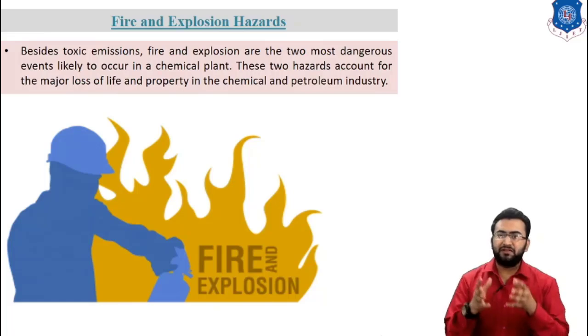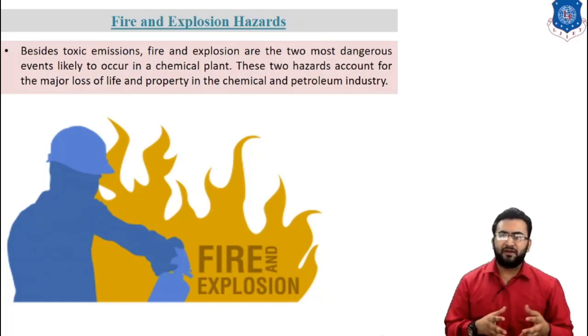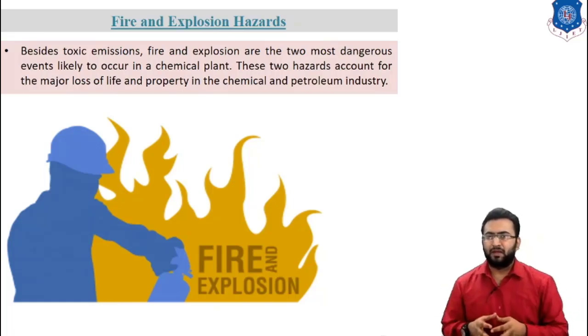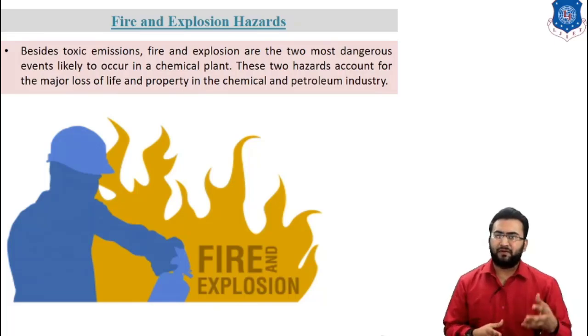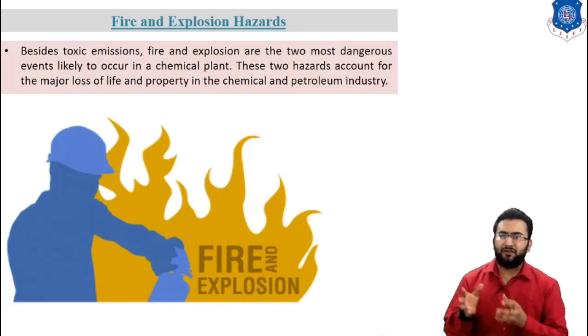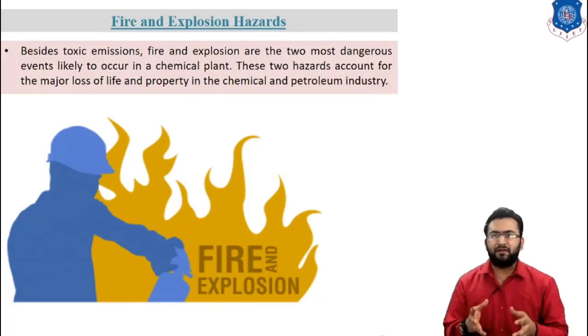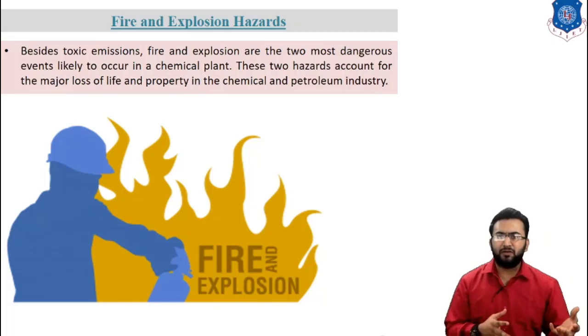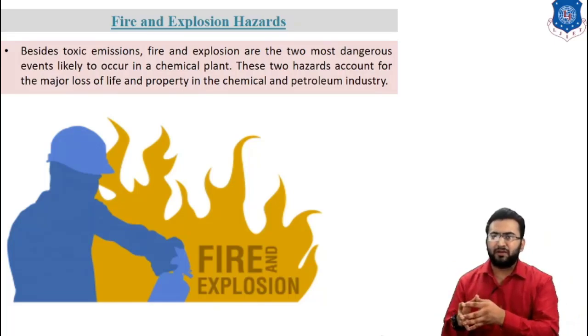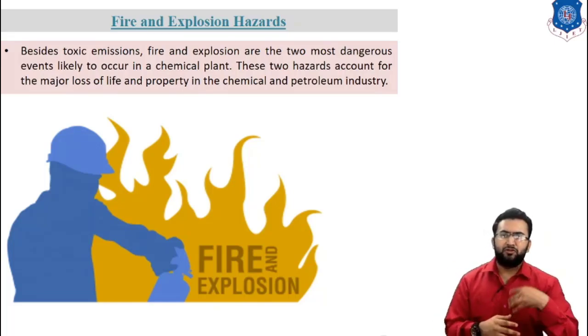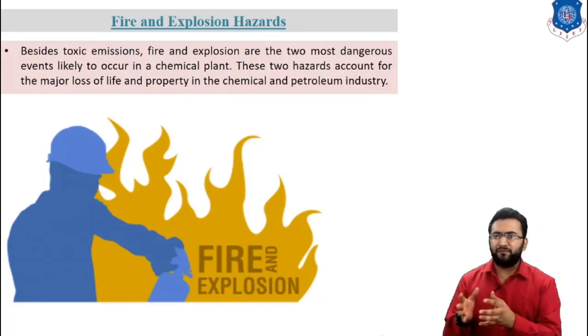An explosion is a sudden release of energy because of a pressure wave. An explosion can occur without a fire, such as a failure through overpressure of a steam boiler. It is necessary to distinguish between detonation and deflagration when describing the explosion of a flammable mixture. The chance that fire or explosion will spread to adjoining units can be significantly reduced by careful plant layout and judicious choice of construction materials.